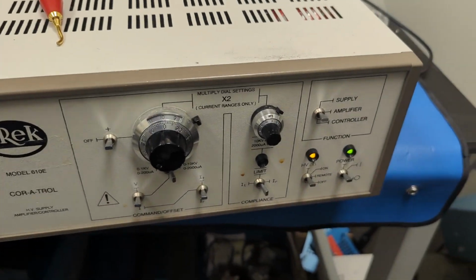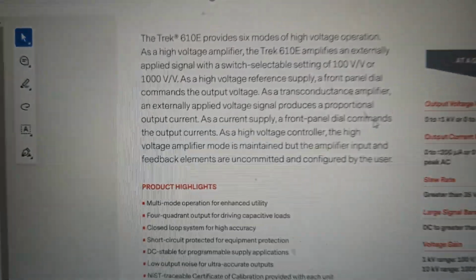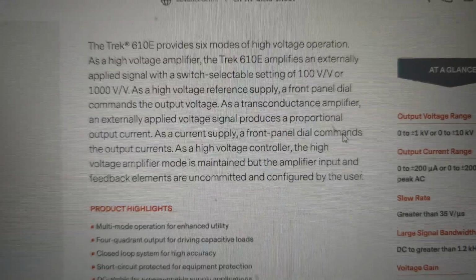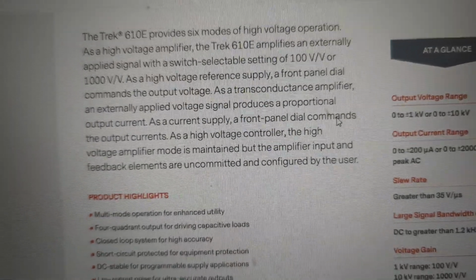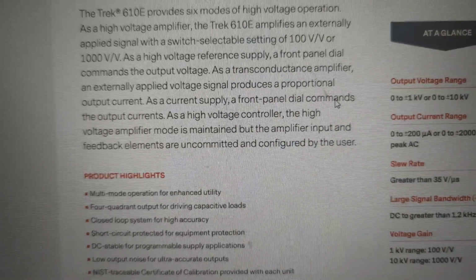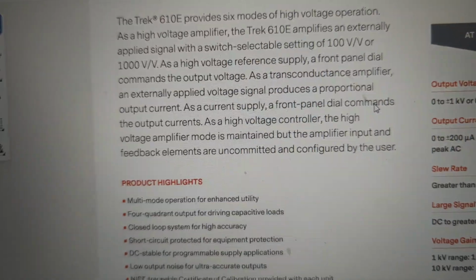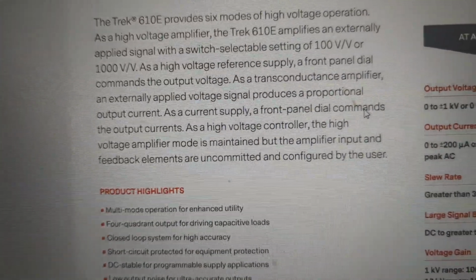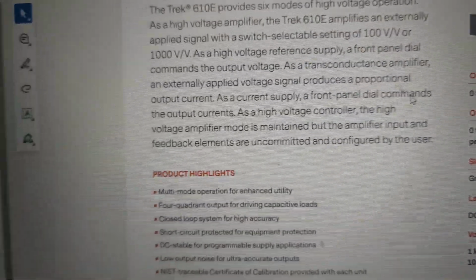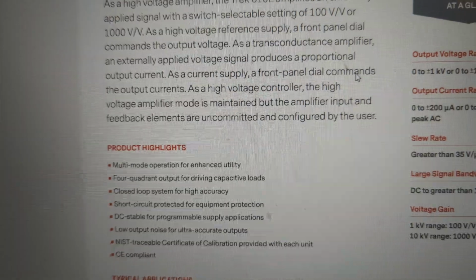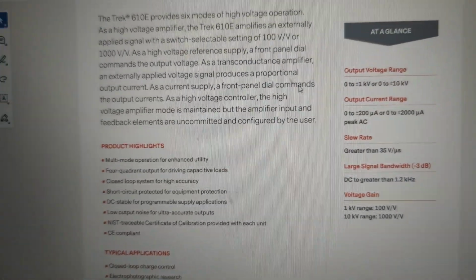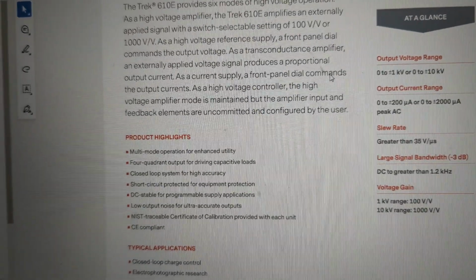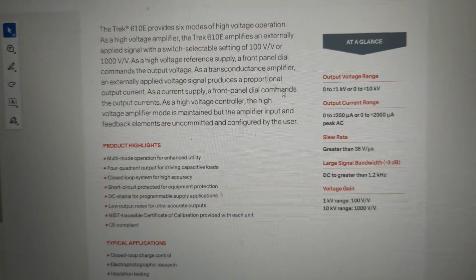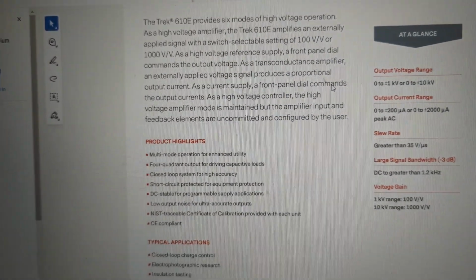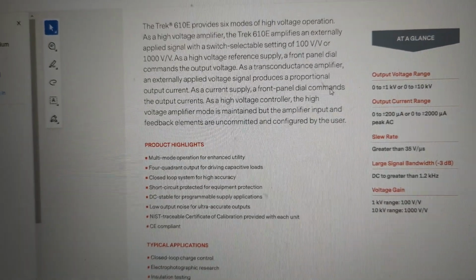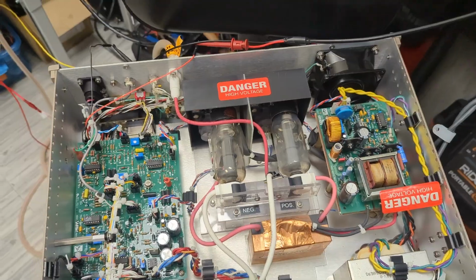I would like to try and test out the amplifier as well. The amplifier portion of the unit works like this. You can apply an external signal, and using those same settings, the 0 to 1 kilovolt or 0 to 10 kilovolt, these are your options for amplification. So it can amplify at 100 volts per volt or 1,000 volts per volt, which is pretty awesome. I was thinking of applying some sort of signal with one of the function generators or pulse generators, and using the high voltage differential probe again to check out the waveform from the amplifier.